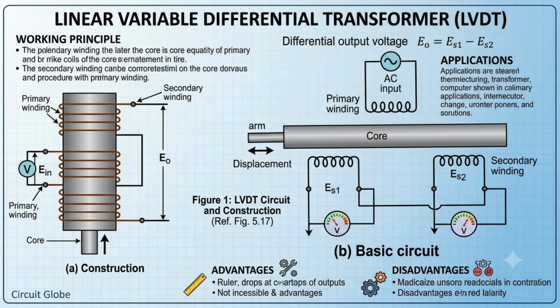The LVDT has very low hysteresis, hence repeatability is excellent under all conditions. It is rugged in construction, so it can tolerate shocks and vibration without any effect. It is simple in construction, and by virtue of being small and light in weight, it is very stable and easy to align and maintain. Most LVDTs consume less than 1 watt of power.